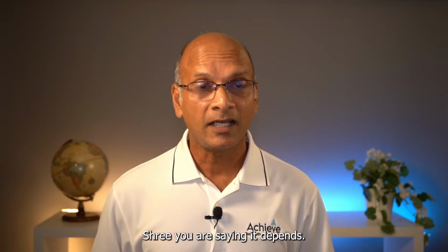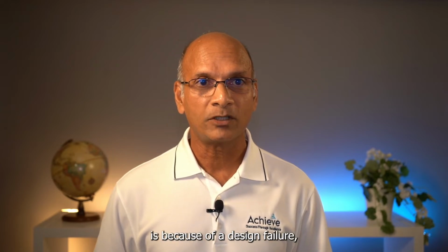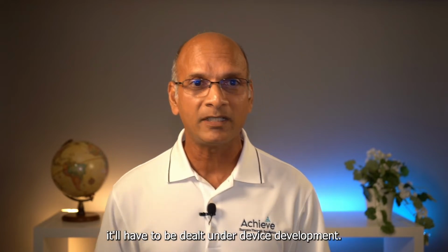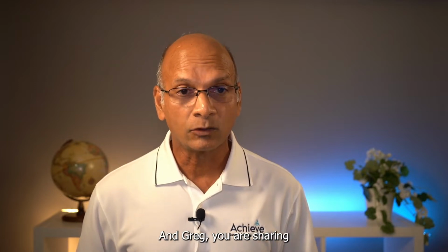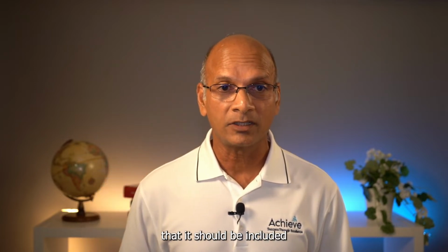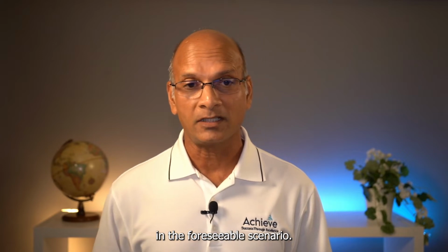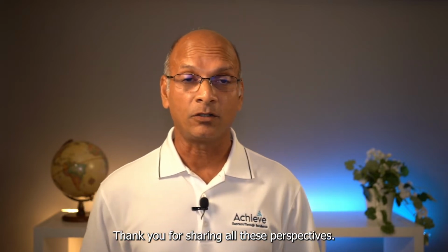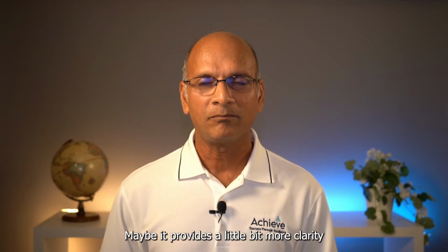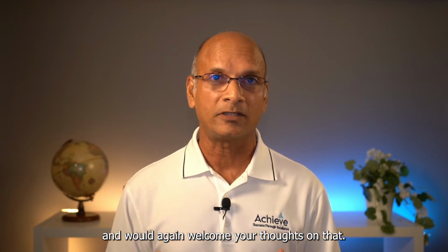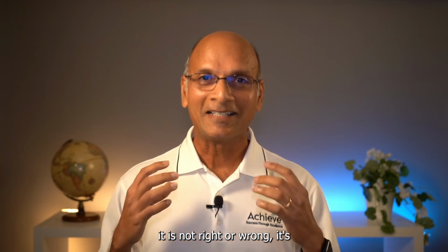Shri, you are saying it depends. If the explant is because of a design failure, it will have to be dealt with under device development. Patient-related factors may be treated like P2 in IVDs, out of the control of the manufacturer. And Greg, you are sharing that it should be included in the foreseeable scenario. Thank you for sharing all these perspectives. So let me share with you a few more slides. Maybe it provides a little bit more clarity and would again welcome your thoughts on that. And again, I'll emphasize, it is not right or wrong.